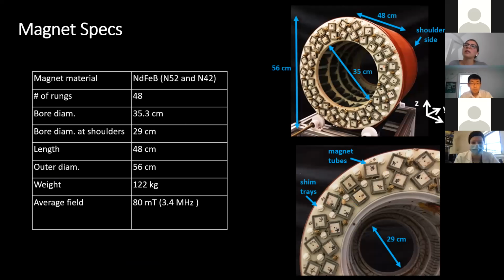Here are the resulting magnet specs. Again, it's made out of these neodymium N52 and N42 grade magnets. It has 48 magnet rungs. The bore diameter is about 35 centimeters. The bore diameter at the shoulder, because of that booster ring of magnets, is a little bit smaller at 29 centimeters. The length of the cylinder is 48 centimeters, and the outer diameter is 56 centimeters. The weight of the magnet is only 122 kilograms, and the average field is 80 millitesla. So again, this is quite a low field compared to conventional scanners, which are generally 1.5 T or 3 T.